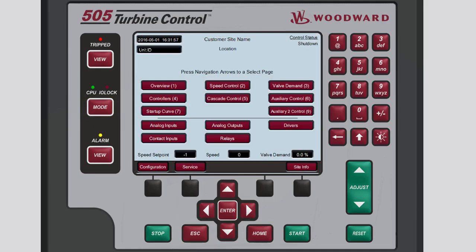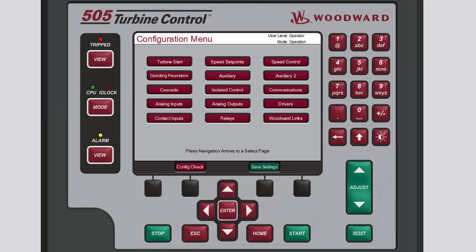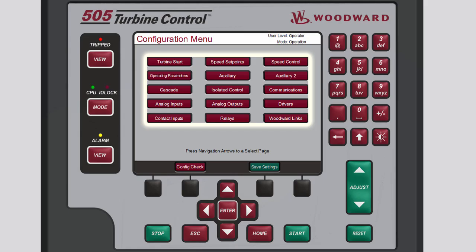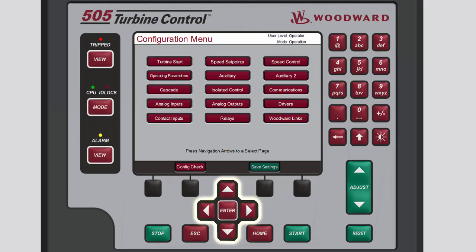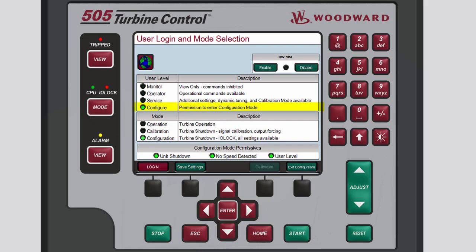Now we'll show you how to access the Configuration Menu and the Service Menu screens. To open the Configuration Menu from the Home screen, press the black Function key below Configuration. The Configuration Menu contains navigation buttons to all of the features and options of the 505. To select any of these buttons, use the navigation crosskeys to highlight the applicable button, then press Enter. To make changes from the Configuration Menu, you must be logged in at the Configure User Level and the unit must be placed in Configuration Mode.